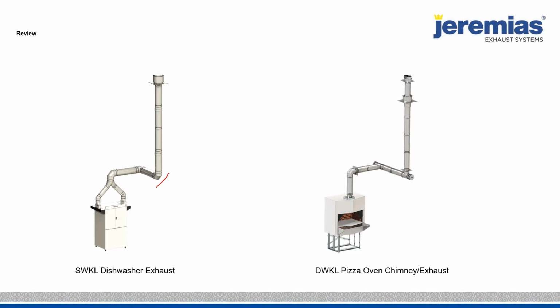Pizza ovens, wood burning pizza ovens, have become popular. There's a little add-on to the 103 called HT, UL 103 HT. Only 3 of us manufacturers have that HT added on. That's a 2100 degree burnout for 10 minutes, 3 times to make sure that the product can handle above 2000 degrees.